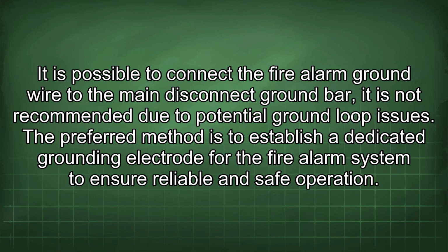It is possible to connect the fire alarm ground wire to the main disconnect ground bar. It is not recommended due to potential ground loop issues. The preferred method is to establish a dedicated grounding electrode for the fire alarm system to ensure reliable and safe operation.